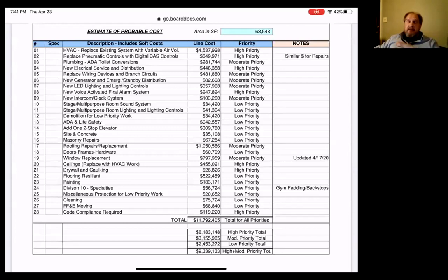So, there's other things I'll throw in there. With the pneumatic control, you are limited. There's things it can't do for you. Night setbacks are complicated. Tracking outdoor temperature to ramp your system back, you can get more finite control with digital, is really what I'm getting to. You can also control it remotely, where you can't really do that with pneumatics without a lot of complicated interface. Anyway, I'm looking at this saying that's always been kind of on the table. That system's been begging to be replaced.